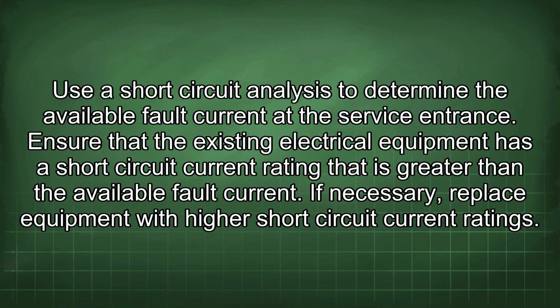Use a short-circuit analysis to determine the available fault currents at the service entrance. Ensure that the existing electrical equipment has a short circuit current rating that is greater than the available fault current. If necessary, replace equipment with higher short circuit current ratings.